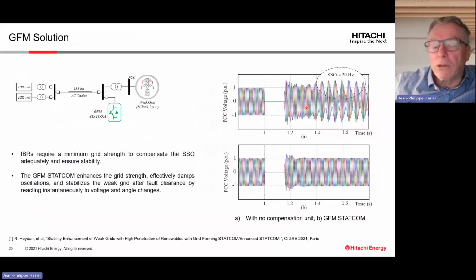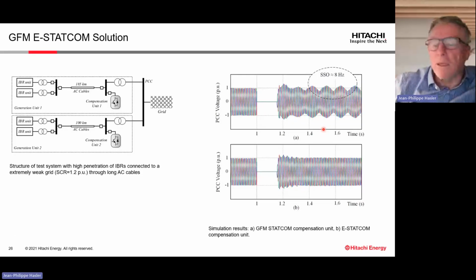Proof of concept, I will just do very fast, if I'm allowed. This is just to compare two results. When we have, say, a three-phase fault in a wind farm application, the first purpose of the E-STATCOM, after voltage recovery, is to damp the overvoltage. That is the most important. And after a while, it is to damp the subsynchronous resonance you can get between a wind farm, for example, and the grid. And that is probably the same example. Okay, I'm sorry to be too long.